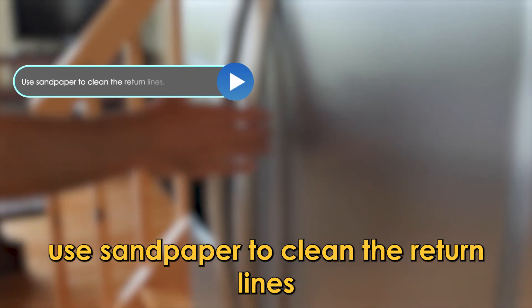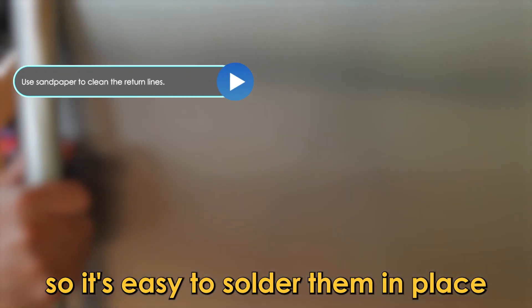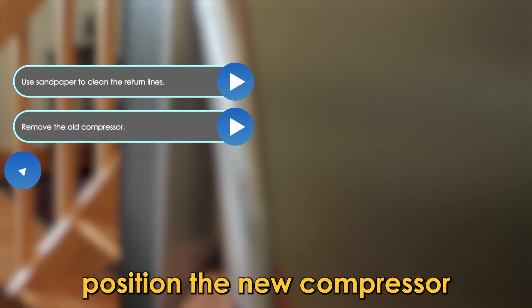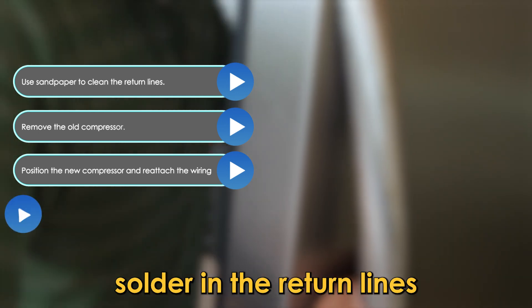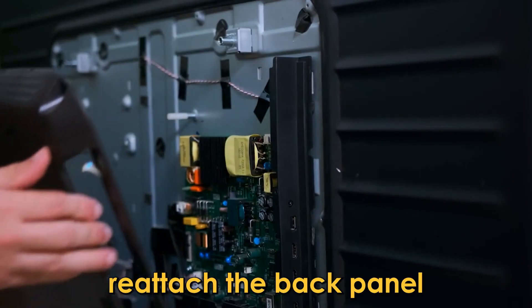Use sandpaper to clean the return lines so it's easy to solder them in place. Remove the old compressor. Position the new compressor and reattach the wiring and mounting bolts. Solder in the return lines. Reattach the back panel.